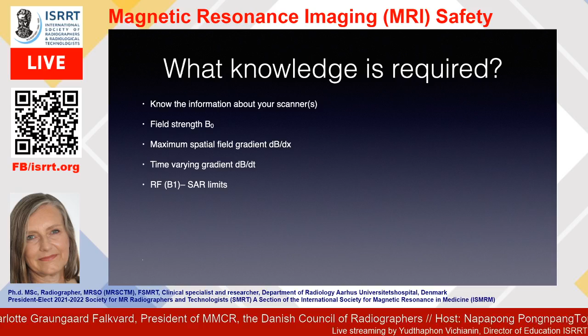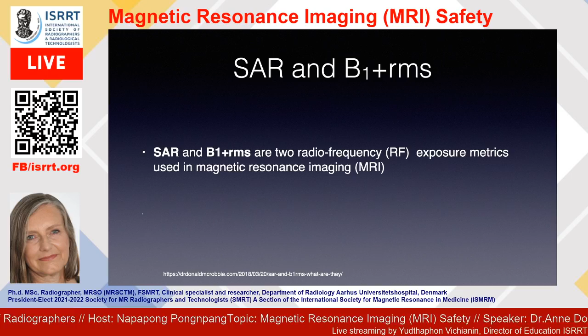So let's just use a short time on SAR and B1 plus RMS. SAR and B1 plus RMS are two radio frequency exposure metrics used in magnetic resonance. SAR is the specific absorption rate, and the RF power transmitted in watts into the patient divided by the patient's body weight gives us the watts per kilo. And we have some allowable SAR limits. The normal operating mode is 2 watts per kilo, and the first level controlled mode is 4 watts per kilo.